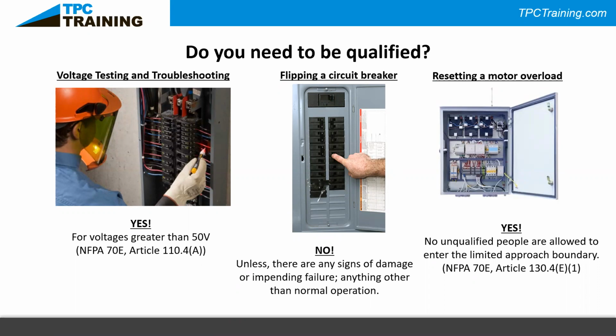Even if you don't intend to touch it, it can touch you—say a wire is loose, or a connection is loose enough that an arc comes right out at you as soon as you open the door. You don't want to put yourself in harm's way. You need someone qualified who knows the proper PPE requirements to protect themselves when opening this door. This comes back to: no unqualified people are ever allowed to enter the limited approach boundary of the equipment.